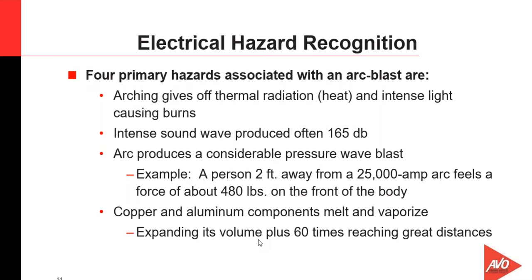The arc itself can produce a pressure wave. When you have copper and aluminum melting and going through the melting stage actually to a vapor, its expansion rate is extremely high and it rivals dynamite. The pressure wave generates intense pressure on the equipment, and also intense pressure on the individual. With a 25,000 amp arc, 2 feet away from that, a person's getting about 480 pounds on the front of the body. That may not sound like a lot, but in a couple of cycles, that's a tremendous amount of pressure.